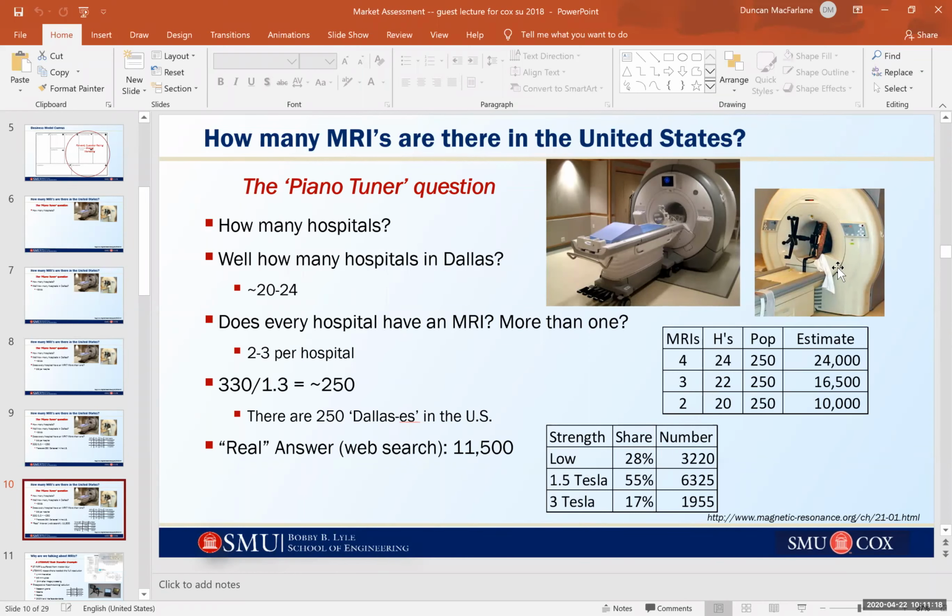If you have a piece of metal, like a chair sitting across the room, this thing will pick it up and suck it right into its core. It's a really powerful field. A 1 Tesla magnet is really powerful, and we're talking about 3 Teslas down here in this high end, roughly 20% of the market area.